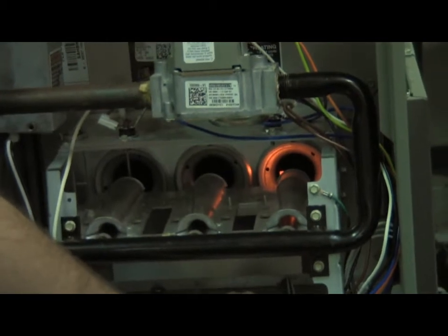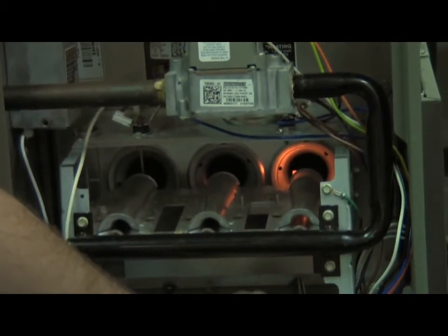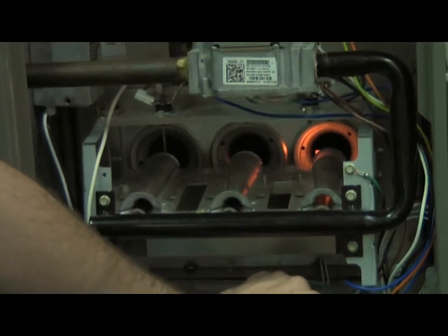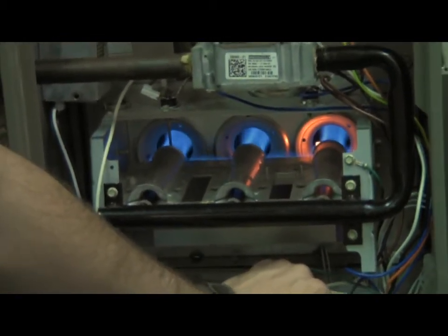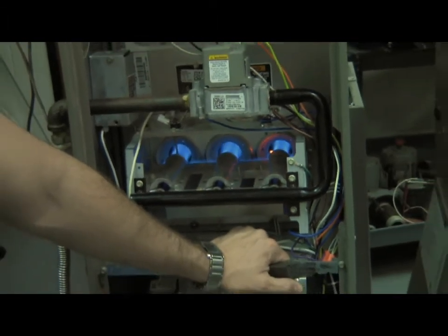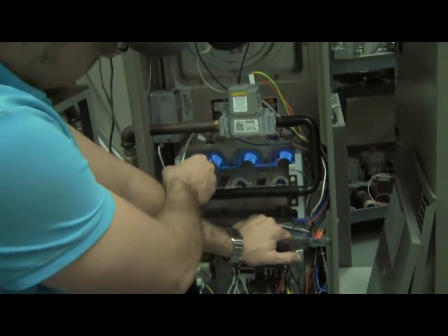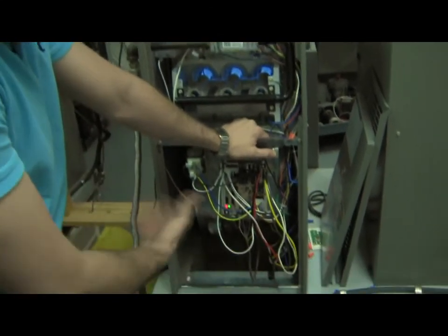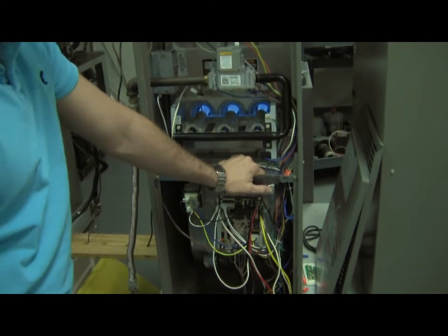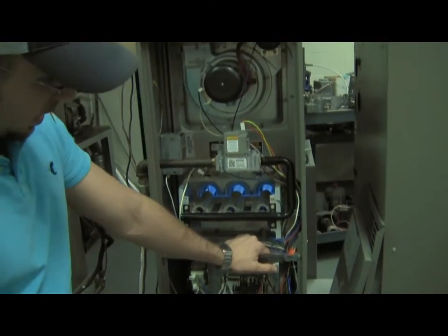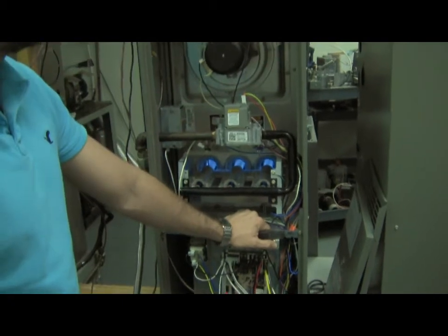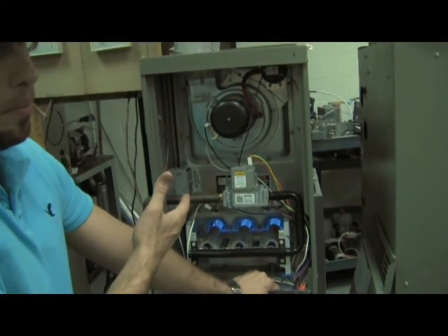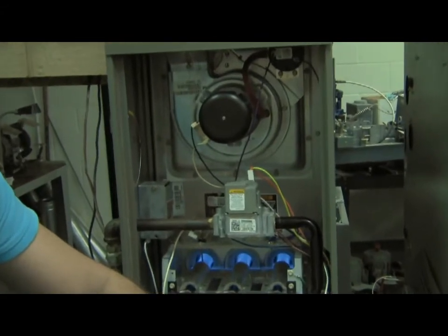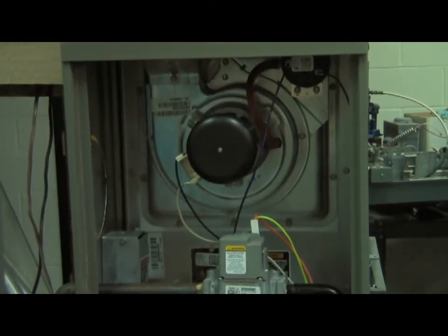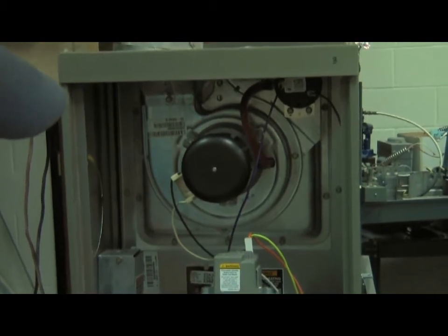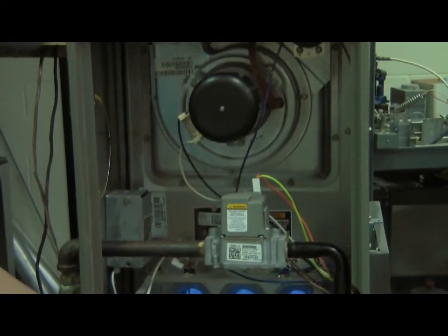Once the igniter's lit, the control board will send a signal to the gas valve to open. Once the gas valve opens, it lights, and the flame sensor sends a signal back to the control board saying that the flame lit. Once it's lit, it'll run for 30 to 45 seconds to let the heat exchanger heat up, and then your blower motor will come on and blow warm air into the place. Right, into wherever it's going.